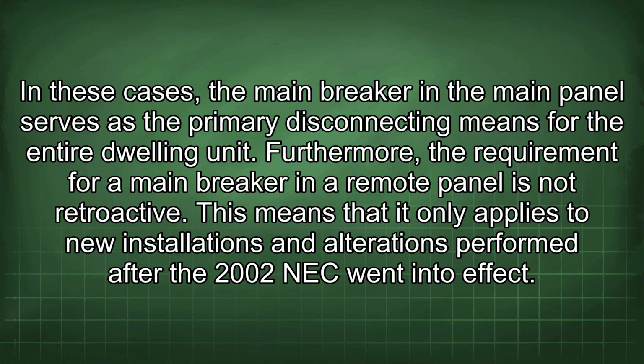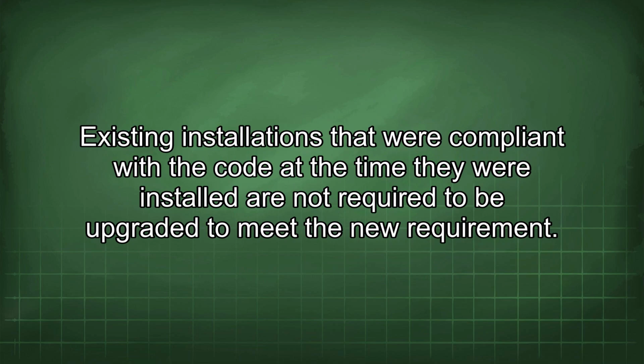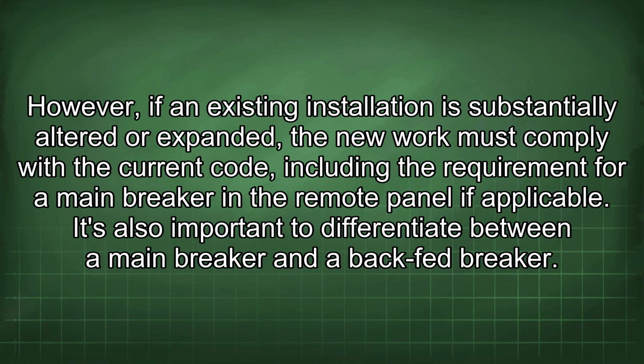Furthermore, the requirement for a main breaker in a remote panel is not retroactive. This means that it only applies to new installations and alterations performed after the 2002 NEC went into effect. Existing installations that were compliant with the code at the time they were installed are not required to be upgraded to meet the new requirement. However, if an existing installation is substantially altered or expanded, the new work must comply with the current code, including the requirement for a main breaker in the remote panel if applicable. It's also important to differentiate between a main breaker and a backfed breaker.